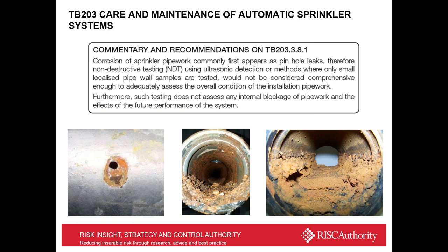We are confirming that NDT, ultrasonic testing, and small pipe samples, where we're just taking small samples of the pipe wall, this kind of testing does not assess any internal blockage of the pipework. So it's not considered a comprehensive enough assessment of the overall condition of the pipework. So this is a new requirement in TB203 for 25-year pipe testing.